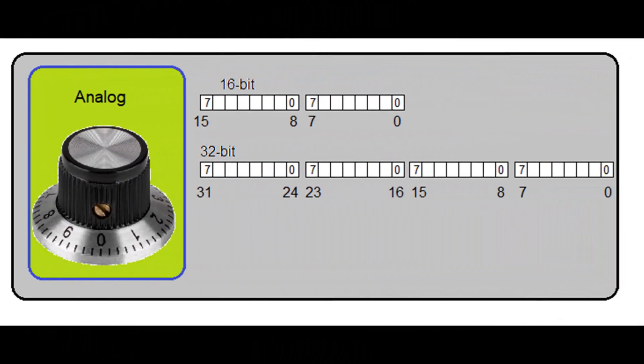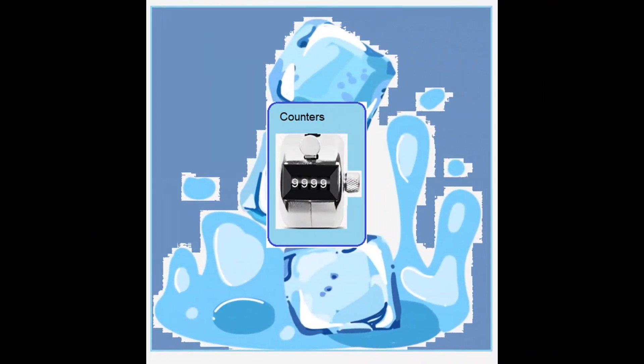Next we have analog, which is the SCADA and DNP term. In DNP3, analog inputs are 16 or 32-bit signed numbers. For the SCADA term counter, DNP has two types: the basic counter input — which I will normally call a running counter — is a 16 or 32-bit number that counts occurrences of a certain field event; the most common case counts power usage. An outstation may also maintain a frozen counter value for each associated running counter.